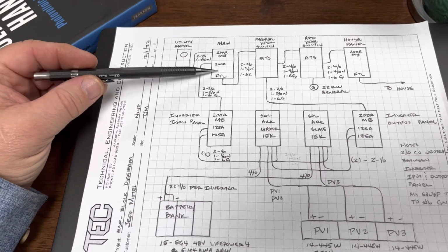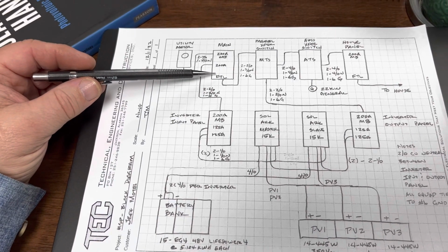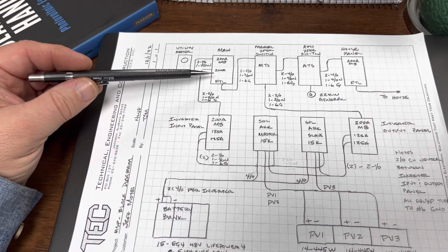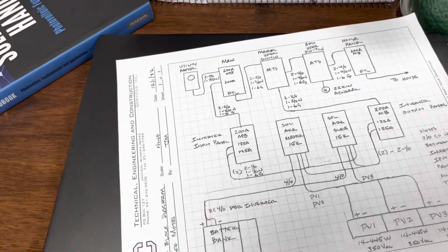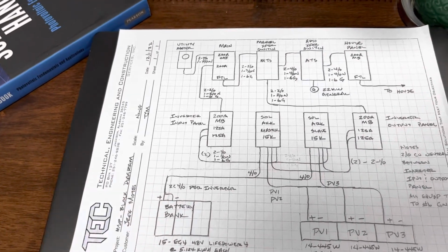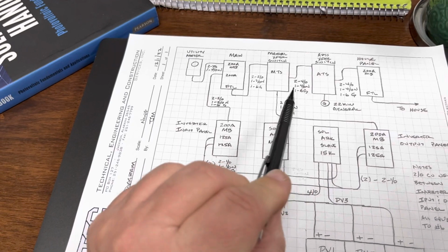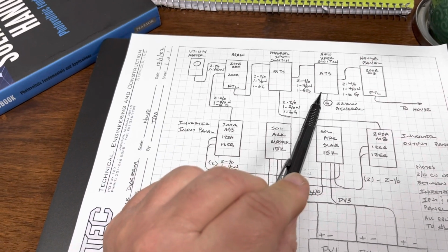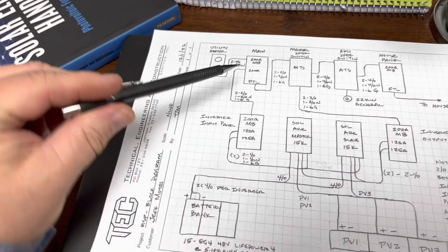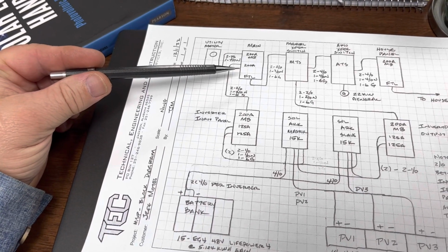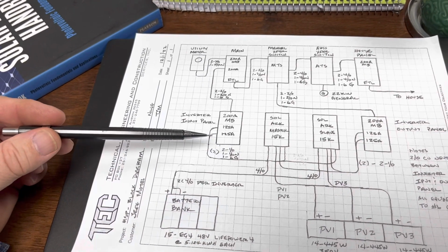Because this is my first panel for my utility meter. So, at this panel, my neutral and my ground are bonded together, and nowhere else. So I had to modify my wiring at the automatic transfer switch, because before I started, this was my first panel from my meter. This was a service entrance rated switch, and my neutral and ground were bonded here. So I had to remove that bond because I was now bonding over here. Everywhere else, the neutral and the ground are not connected.